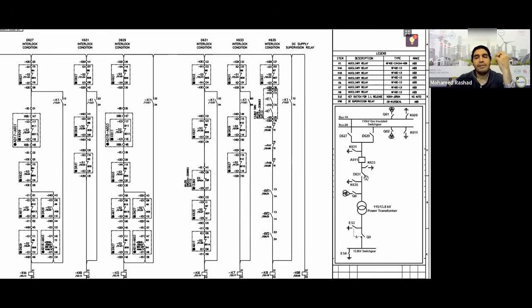Well, in switchgear you always find interlocking. If any of you have worked in switchgear stations, you always find the earth switch on the switchgear side is operated manually, mechanically. All right, very good. So now, if you close this disconnector switch, what prevents you from going to the earth switch, opening these shutters, installing the handle, and closing the earth switch? There's nothing stopping you, right? Am I wrong? That's why they do a slightly advanced move.